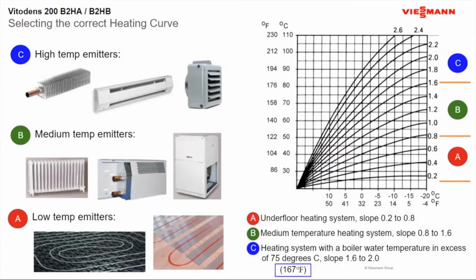Then on the same page in the manual, it gives you the A, B, and C, and gives you some starting points for your radiant. So A would be anywhere from 0.2 to 0.8. B would be anywhere from 0.8 up to 1.6. And these are starting points. I have done some radiator jobs where I was more down at the lower temperature settings. They hold the heat for a long period of time as well. So it's a good emitter when you're doing constant circulation, things to that nature.